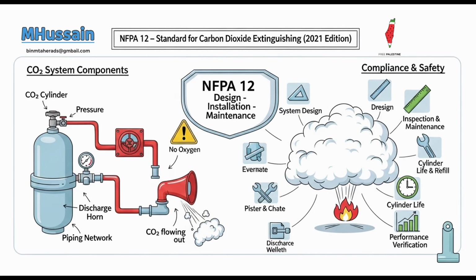Are there other conditions that affect the CO2 quantity, like temperature? Yes, the standard also meticulously accounts for special conditions. If an enclosure is normally above 200 degrees F, 93 degrees C, an additional 1% of CO2 quantity is required for each additional 5 degrees F, 2.8 degrees C, above that baseline. More CO2 needed for hotter rooms. Right. This compensates for the higher ambient temperature, which means the fire is already hotter and the CO2 might dissipate faster, requiring more agent to achieve effective cooling and suppression.